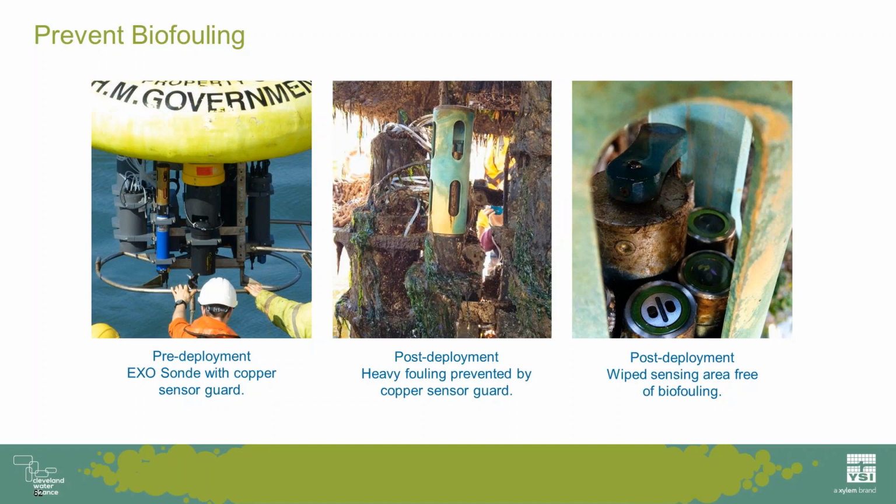We're also showing the usefulness of copper. Copper is toxic to most aquatic organisms, and we have a copper sonde guard that slips over those sensors and which was used in this deployment. As you can see in the middle picture, this was a very high fouling marine environment, but the sonde guard doesn't have hardly any growth on it.